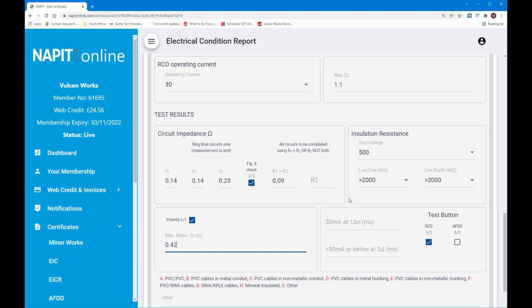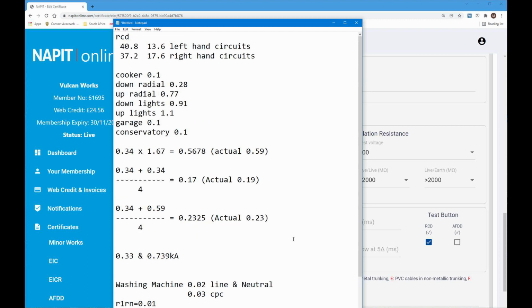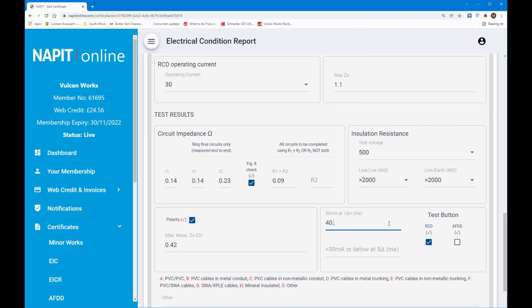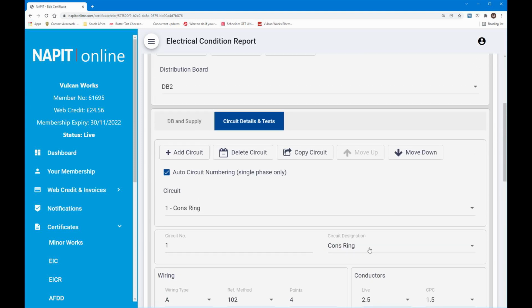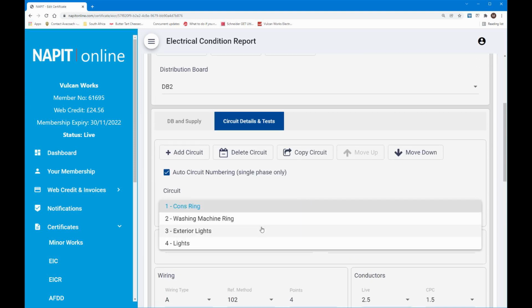And obviously, like I said, we've done the insulation resistance already. And we need to do the test, which is the left-hand circuit, 40.8 and 13.6. So that's that circuit done, and then we've got two more circuits to do. We have the exterior lights for the EICR had a fault. If you remember, they were actually causing problems. I wasn't getting good continuity, I wasn't getting good insulation resistance, so there are no values for the exterior lights because I couldn't do it.